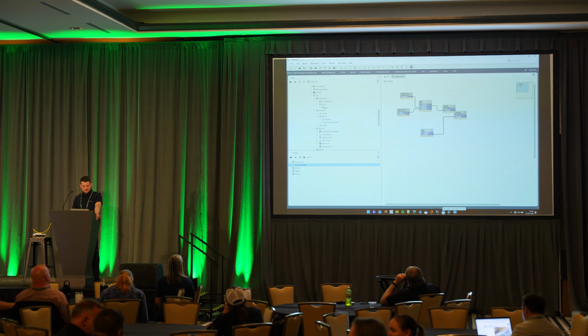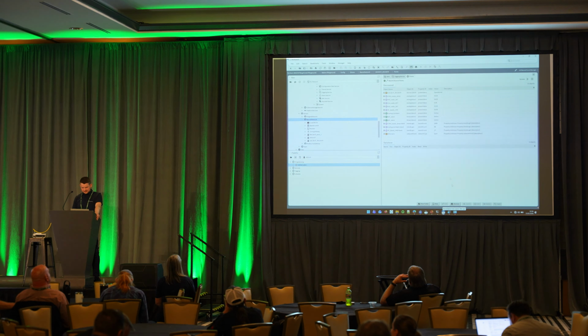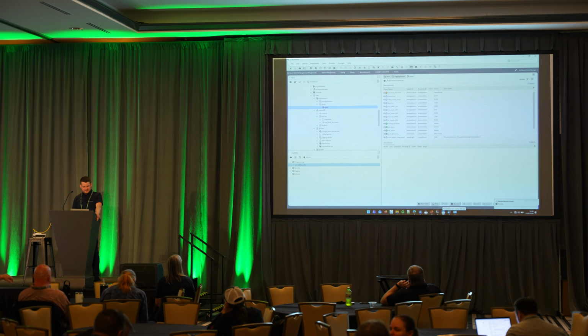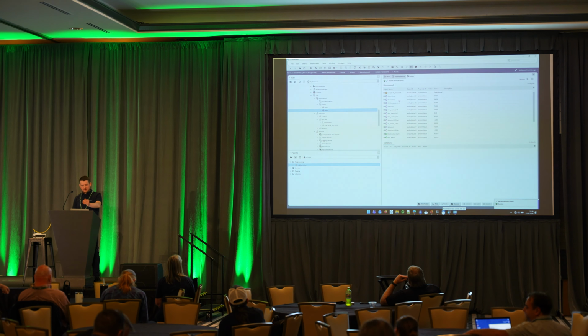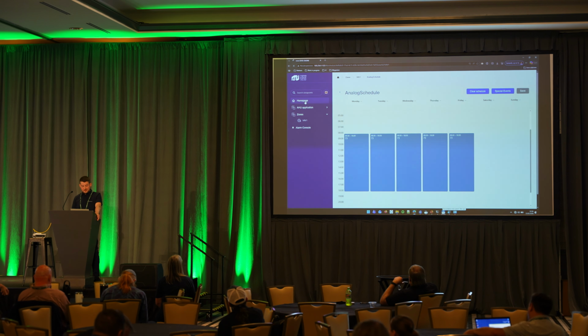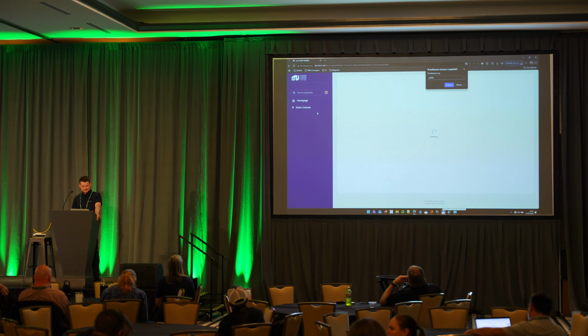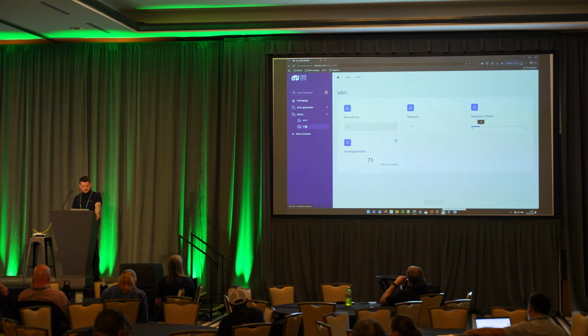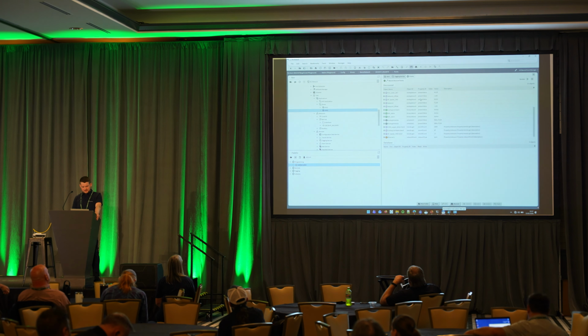What we can do now is go to the BACnet device for a second. So we go into BACnet. I linked my BACnet device here, so we can now discover all those points. As I mentioned, they are natively available. Let's say we have seven of those VEVs available on the network. We can just duplicate this device multiple times, and we just have two. When we click Discover, now we have all of those points available from two VEVs, and this is also going to be visible on the web server just as we speak. So we have zones, now we have two VEVs. We can link those values directly to the VAV we want to work with.